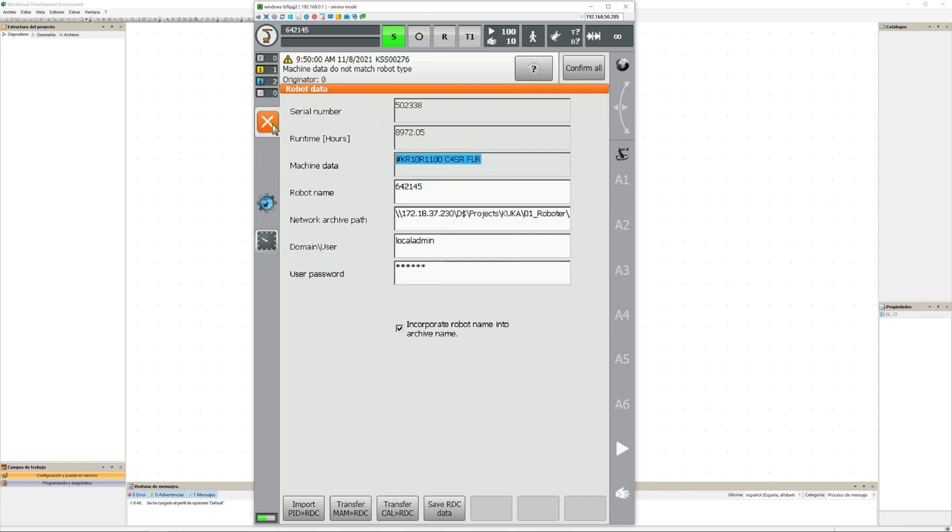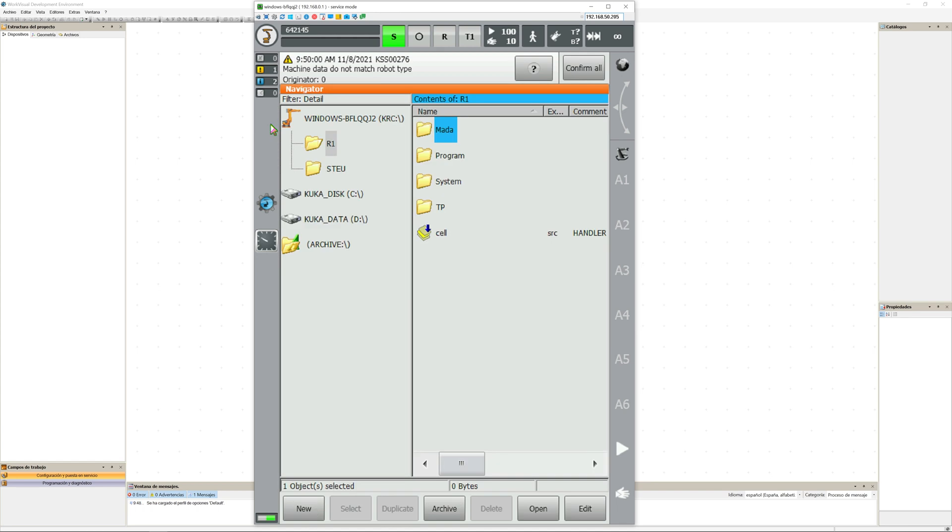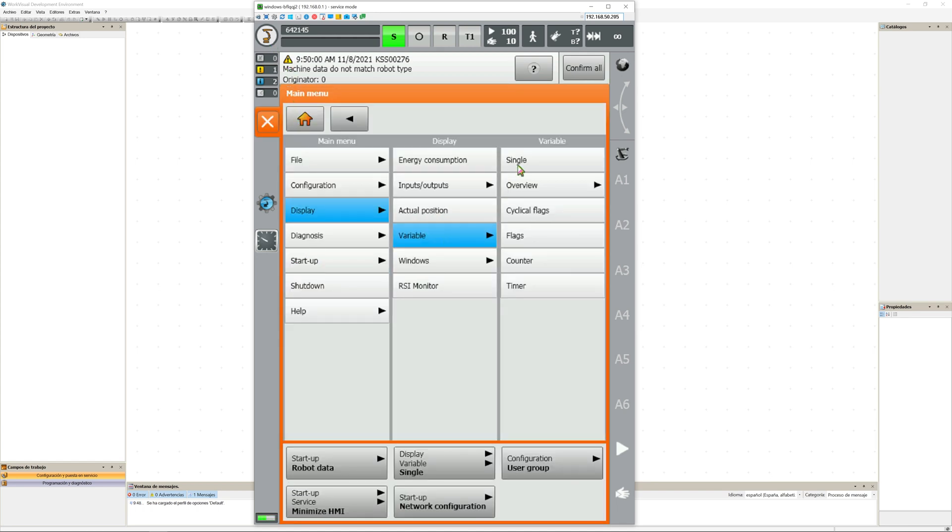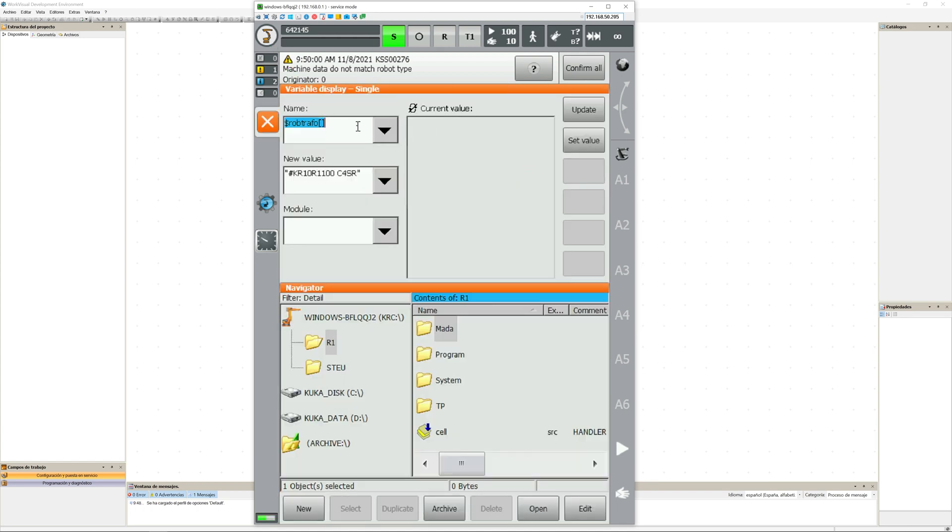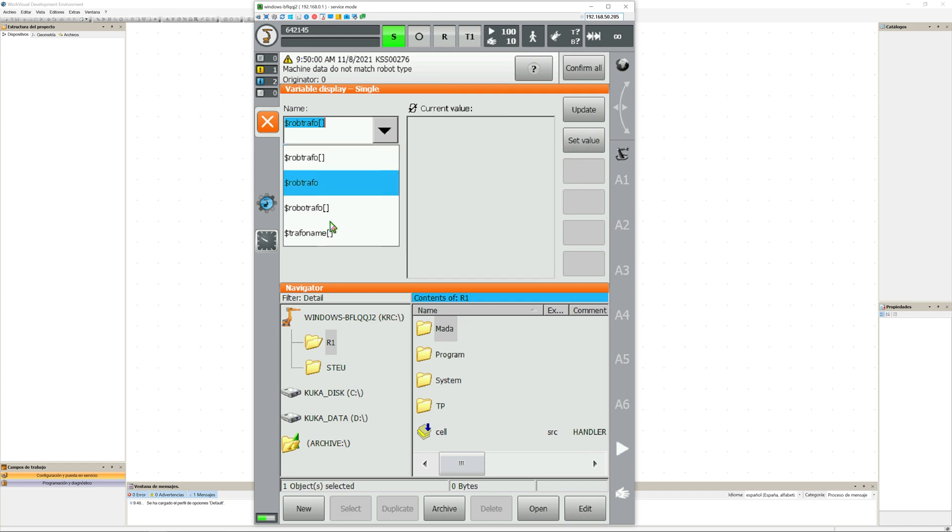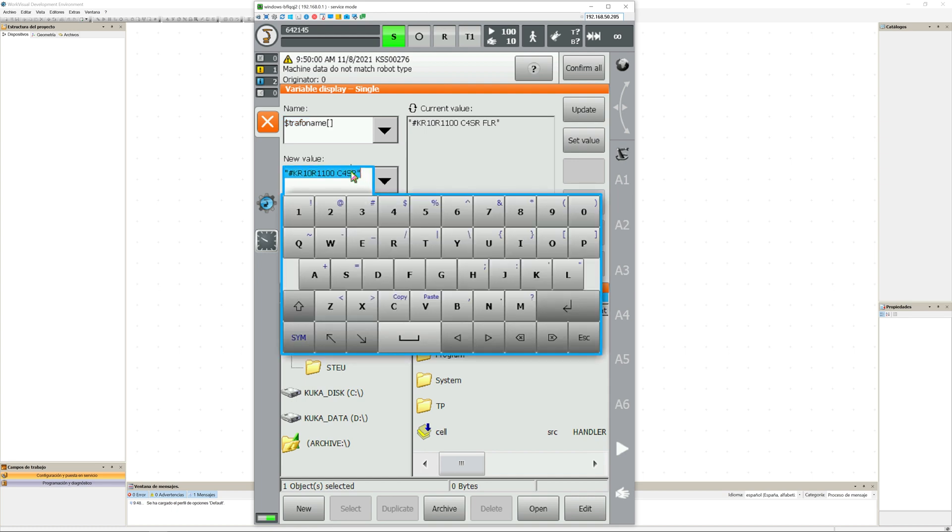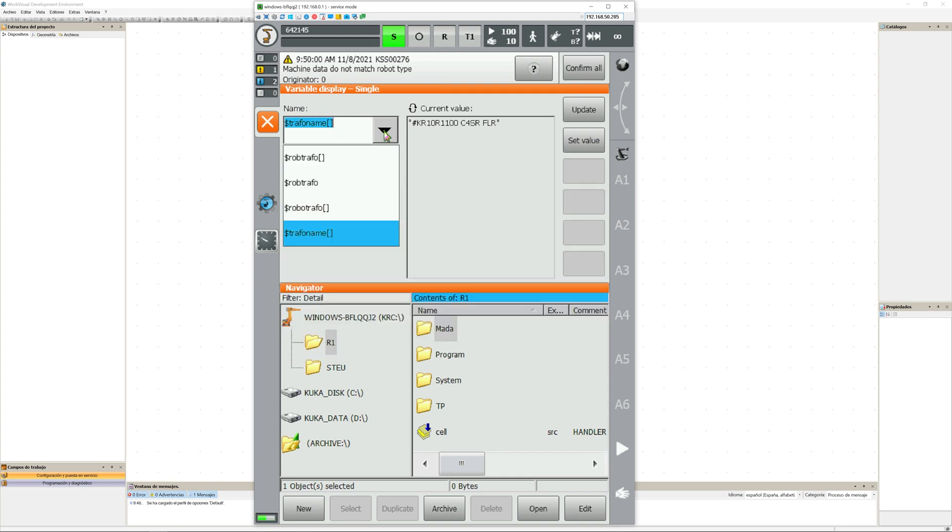As you can see here, you can see the serial number and the runtime, but it says that the machine data is not correct. So we can go into variable, single, and check the $robtrafo. If the $robtrafo differs from the trafoname, then you will encounter this error.